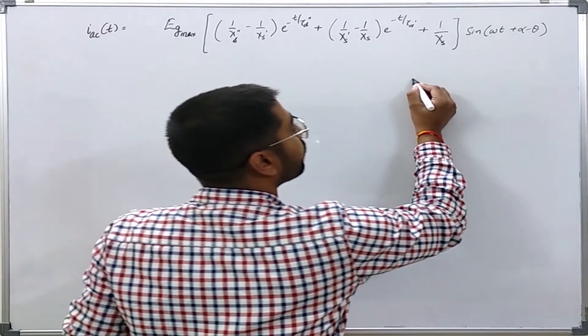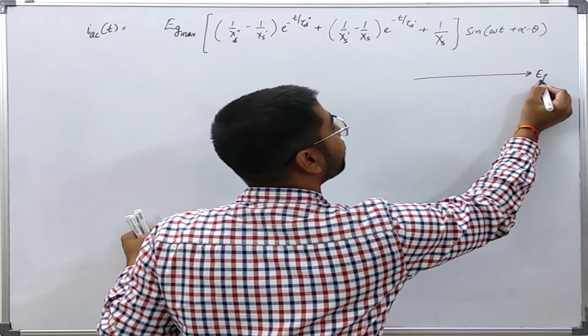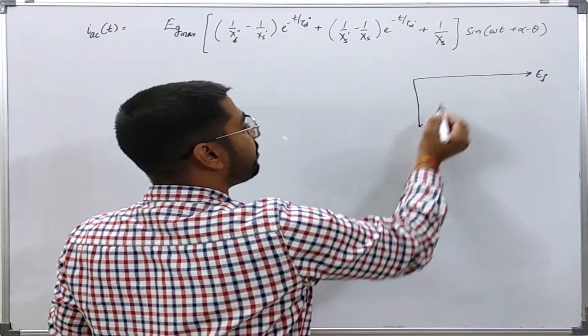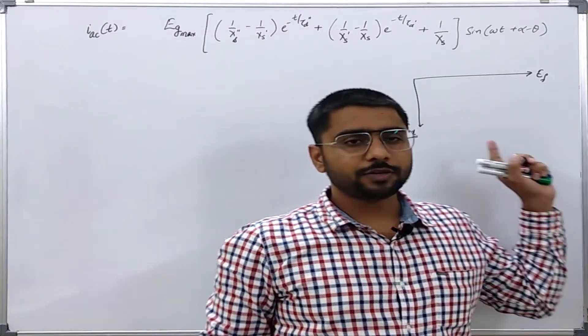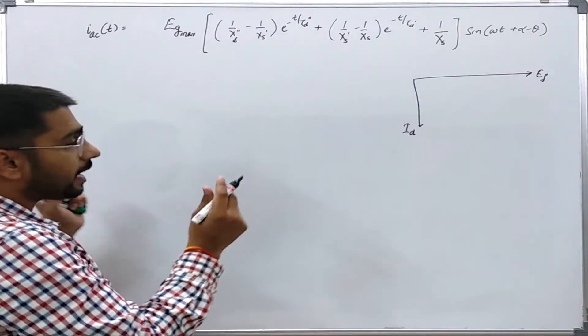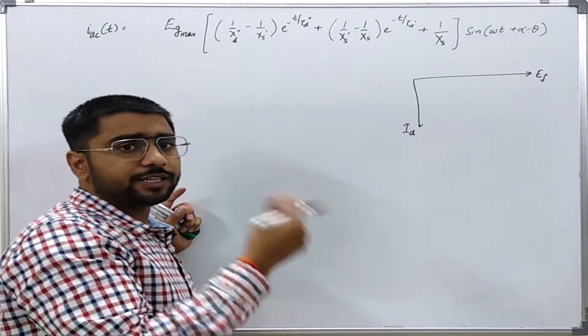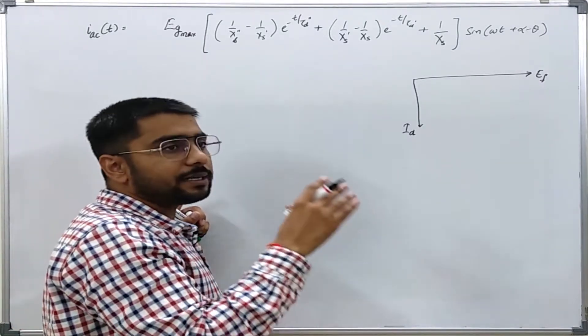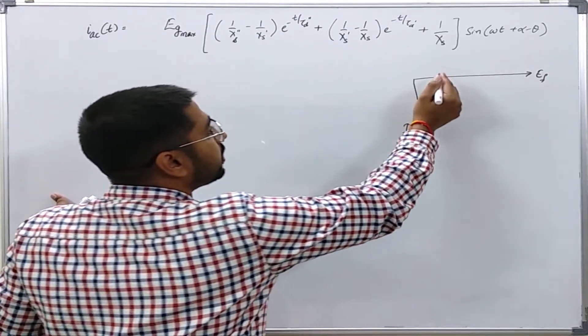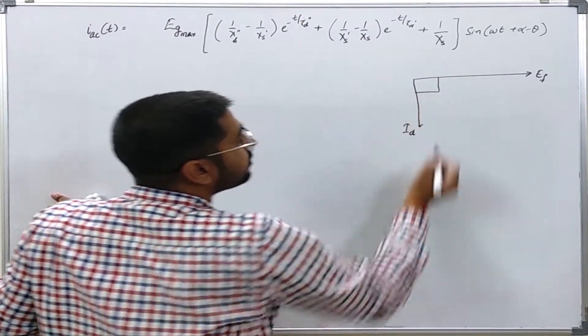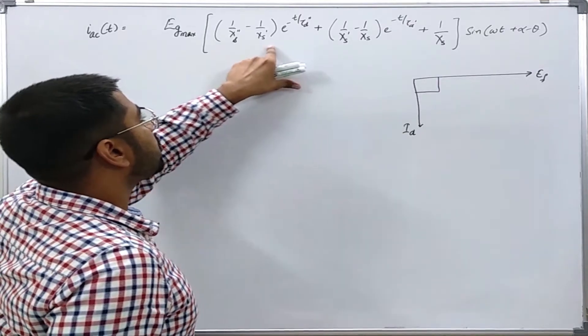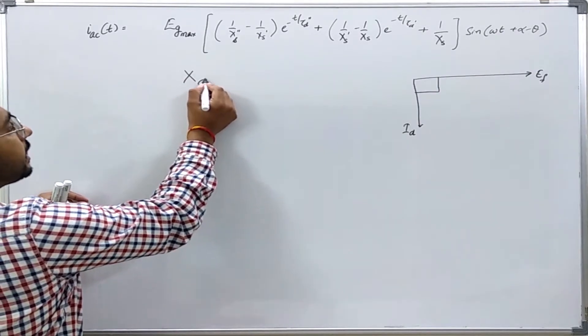Whenever we are dealing with the current which is in quadrature phase with the induced EMF, we use the direct axis reactance. We have already seen that whenever a generator is short-circuited at its terminals, the current is actually very close to the purely inductive current — about 90 degrees out of phase with the induced EMF. So, for the salient pole machine, we only use the direct axis reactance in place of XS.